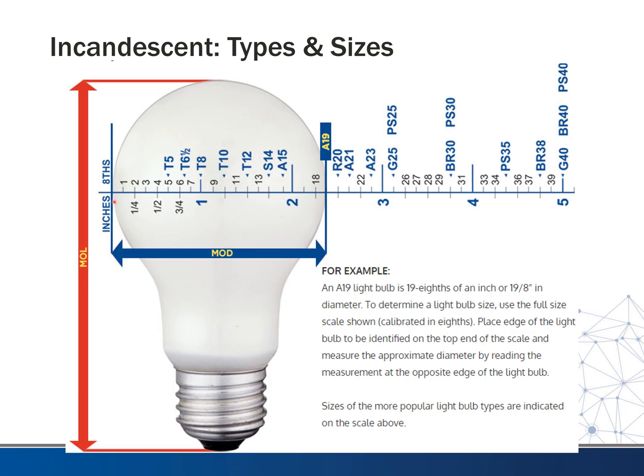The second number has to do with the diameter of the bulb in eighths of an inch. For instance, the common A19 bulb — the most common bulb used in residential applications — has an A shape and 19 means 19 eighths of an inch. You can have an A21 bulb, which is much larger. When you get to fluorescents, you'll see T8s, T5s — anytime you see a number with a light bulb part number, it's usually describing the largest diameter in eighths of an inch. A BR38 or PS30 follow the same convention.